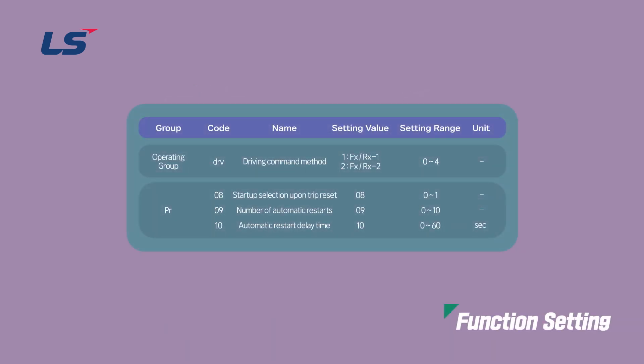Let's see how to set up the Reset and Restart function. To use the Reset and Restart function on the S100, you need to set the Operation Command method to FXRX1 or FXRX2, i.e. Terminal Block Operation command method, in the Operation Group DRV parameter.